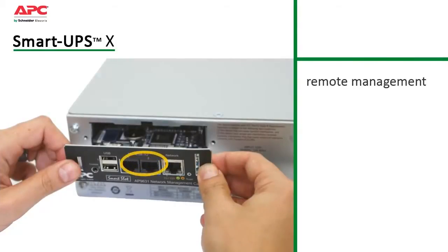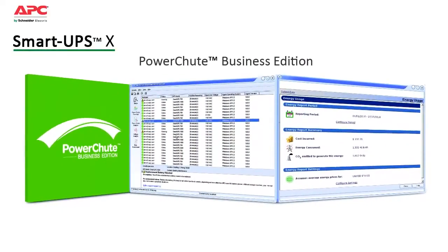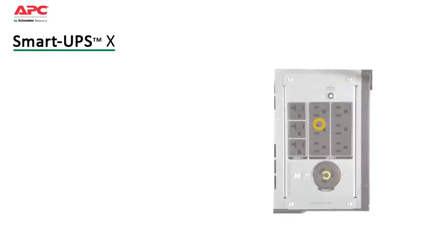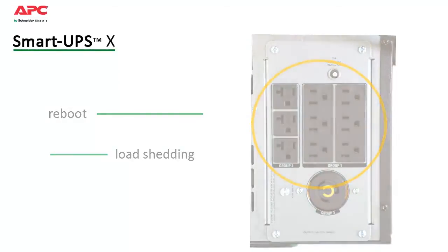SmartUps saves time with easy, convenient remote management via built-in USB serial ports and optional smart slot that accepts a range of accessory cards. Included is APC's PowerChute Business Edition software. Compatible with most server operating systems, it provides innovative monitoring and control and graceful unattended shutdown in extended outage situations. A switched outlet group can be controlled like a UPS within a UPS to further customize settings and provide discrete reboot of hung devices, sequenced on-off and non-critical load shedding to preserve on battery run time.